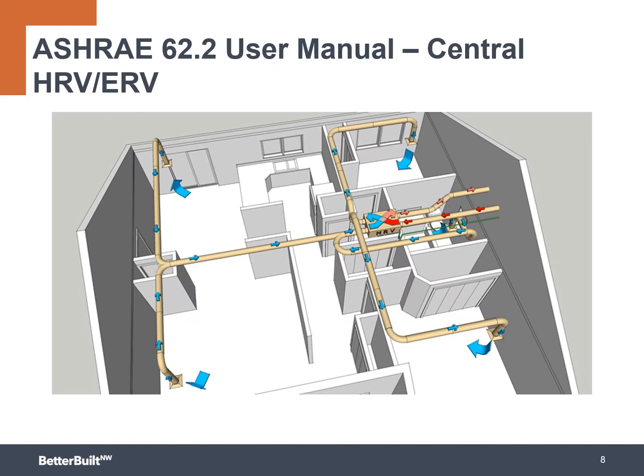This is an alternative visual, and if you don't already use the ASHRAE 62.2 user's manuals, they've made them for the 2010 and for 2019. I recommend the 2019 user manual. It's very good, and what this is just showing you is the general layout of how this system would be set up. As you can see, if you follow the little blue arrows, you can see where air is being pulled from and where air is being delivered to in a home. And this, again, really gets us that ability to be both balanced and distributed.